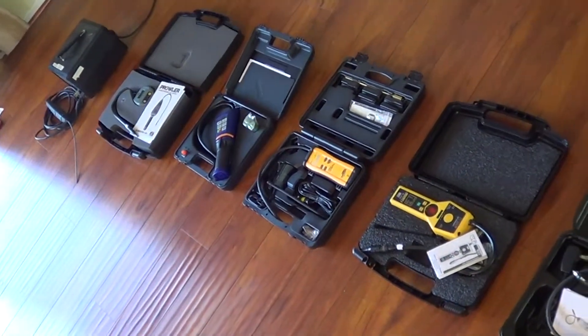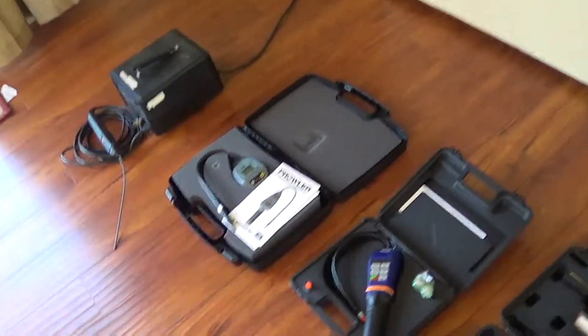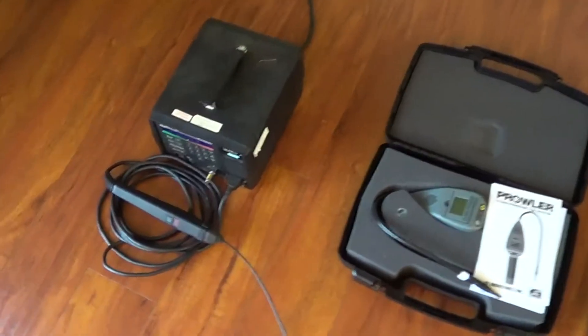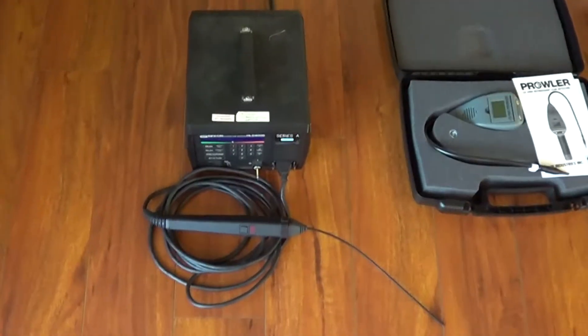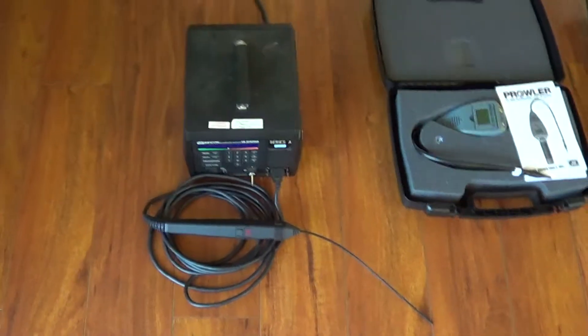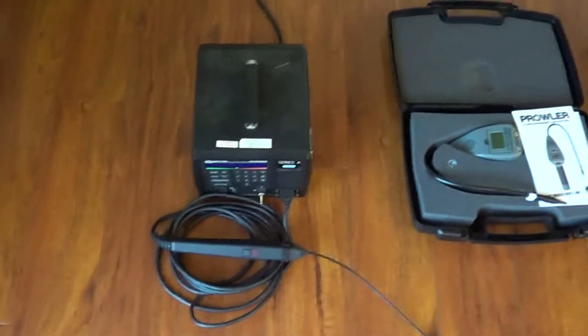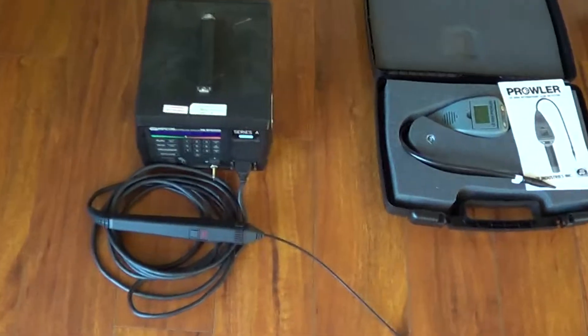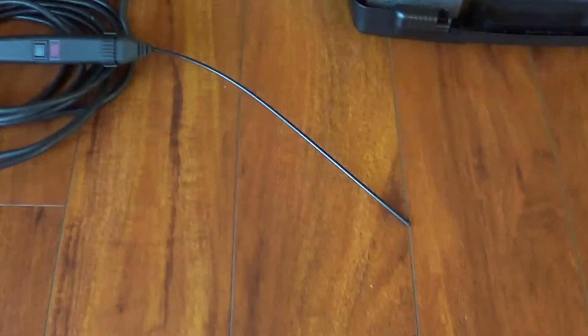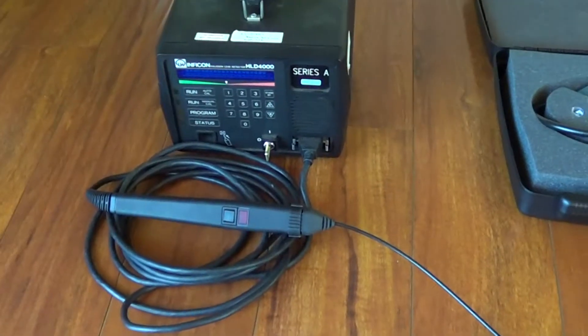As you would imagine, if you spend $8,000 — actually you can get these used for about $1,500 — you'll find your R410A leaks with this one. But it's just a pain: it's five minutes to power on, it's very heavy, the probe can suck up water easily. It's designed to be used in a factory environment.